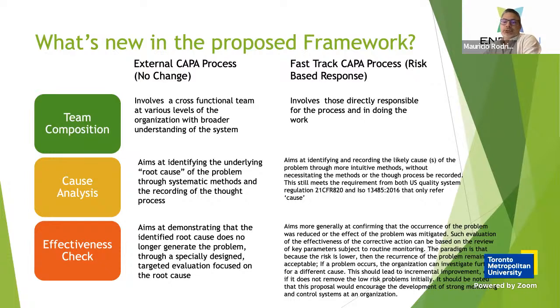To start with team composition, the external CAPA involves a cross-functional team with a broader understanding of the system, whereas the fast-track CAPA involves only those directly responsible for the process and for doing the work. For the cause analysis, there is a difference in documentation requirements. The external CAPA requires the root cause methodology and the actual thought process to be documented within the CAPA record. The fast-track CAPA only requires the cause be documented. So there's a big difference between a root cause and just a cause. Does that not require that the thought process or problem-solving methodology be documented?